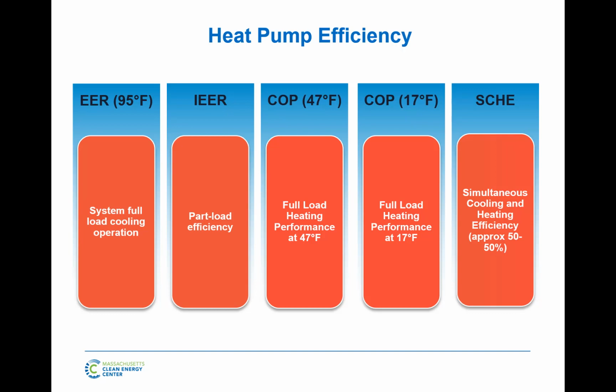So that concept now exists in VRF. And the speed here is your room temperature. So we can program and tweak our systems now to say, okay, I want 72, but you know what? If you're on a peak day on July 31st and that room needs to go to 74 for a few hours, I don't care, because that's going to save me a lot of energy. So this cruise control is usually used with varying the target evaporating refrigerant temperatures and all of that. So that's great. We have all that. It makes our efficiencies way better.